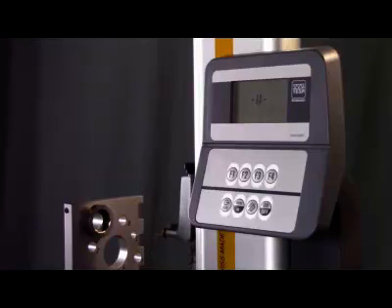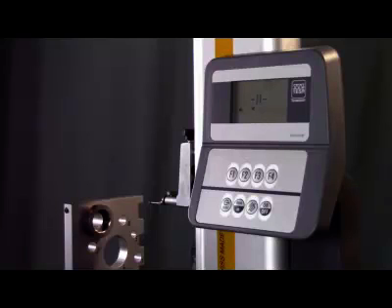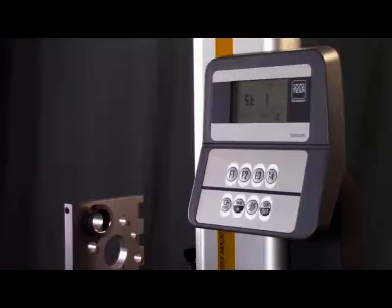Slowly move the measuring head up until you see two triangles appear on the display. Once these arrows are displayed, you can start bringing the probe down the column. Continue bringing the measuring head down until start one is displayed. The tool is now in measuring mode and ready to calibrate.